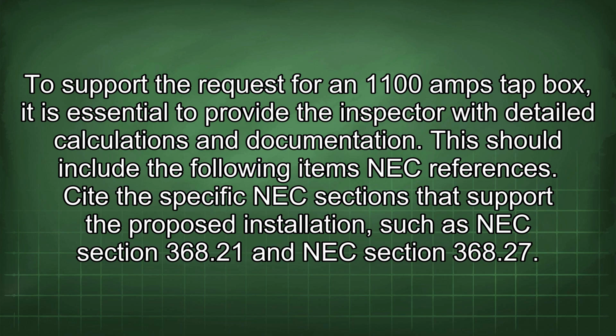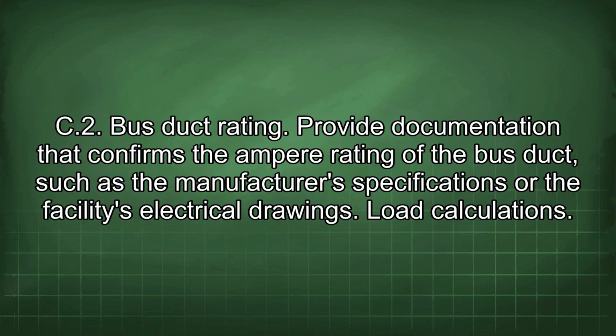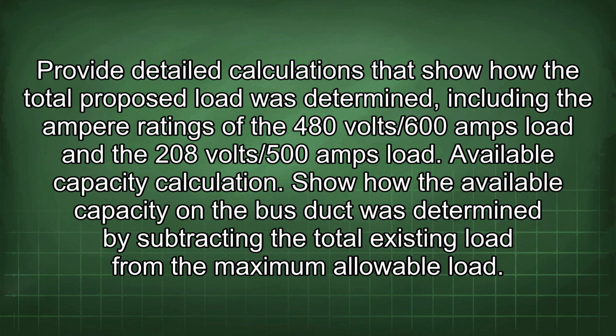Cite the specific NEC sections that support the proposed installation, such as NEC section 368.21 and NEC section 368.27 C2. Bus duct rating. Provide documentation that confirms the ampere rating of the bus duct, such as the manufacturer's specifications or the facility's electrical drawings. Load calculations. Provide detailed calculations that show how the total proposed load was determined, including the ampere ratings of the 480 volts/600 amps load and the 208 volts/500 amps load. Available capacity calculation. Show how the available capacity on the bus duct was determined by subtracting the total existing load from the maximum allowable load.